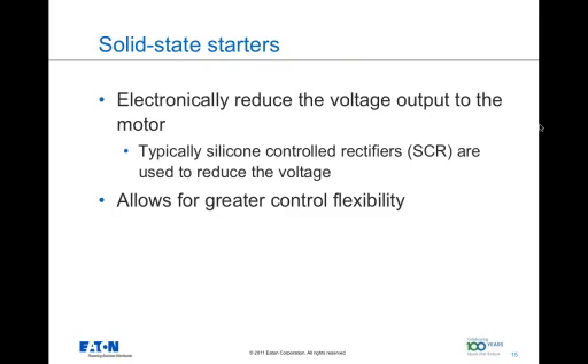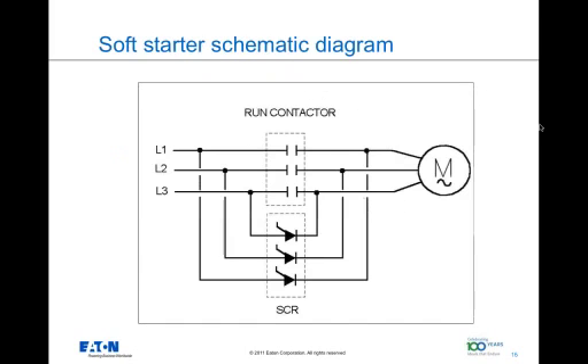And what enables solid-state soft starters to do what they do? They use solid-state switches called silicon-controlled rectifiers to ramp up the voltage. This is a schematic of a typical modern soft starter. In these soft starters, SCRs are engaged during ramp-up and bypass contactors are pulled in after max speed is delivered. This helps to significantly reduce the heat that is generated in the system.